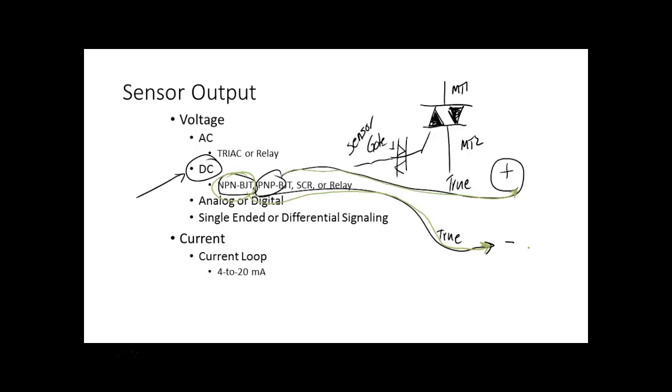A constant current source, let's say, can put out 20 volts. Well, if it requires 4 volts to put 20 milliamps through that conductor, you're okay. But let's say you lose 4 volts down the line. If you try to lose 4 volts because of the resistance of the wire, it'll cause the current to try to go down. But what's going to happen is the output of your constant current source will raise the voltage to cause what? 20 milliamps to flow. So what's nice about the current loop is it's basically immune to the resistance of the wire. It'll keep raising that voltage up until it runs out of voltage, and then you're screwed. And most of them have a really good range. So you see these 20 milliamp current loops run thousands of feet. Thousands of feet.